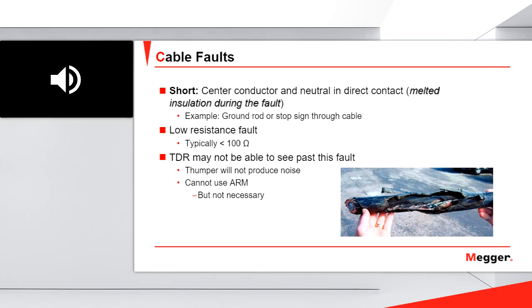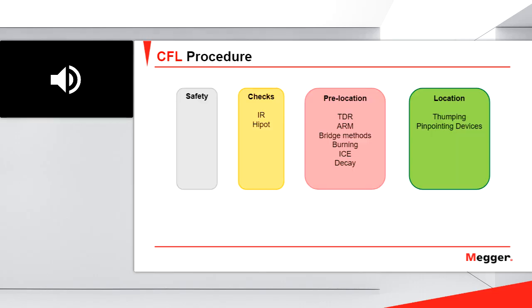So let's now review the modern cable fault location procedure. We have 4 steps. The first one is safety. Safety is always very important when we handle high voltage. And you will see in the next slides that safety is related, in the cable fault location process, to the connections. The connections of the thumper to the faulty cable are very important in terms of safety.